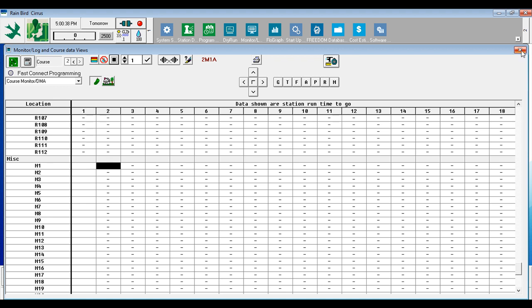Do remember, Rainbird Central Control limits station run time to a maximum of 499 minutes, which is slightly more than 8 hours. For a regular irrigation valve or sprinkler, station run time will never approach that limit. However, if you have external field equipment connected via IC-out and you want to run them for longer durations via Central Control, it could be an issue. For example, your club might have a water feature that needs to run non-stop during open hours, about 15 hours every day. Please watch the Rainbird video on running an IC station for more than 499 minutes to see how that can be accomplished.